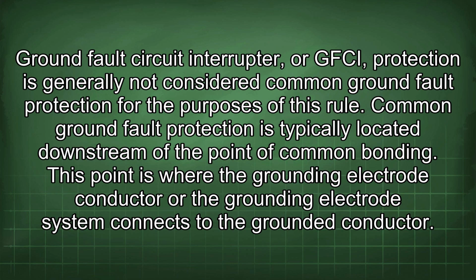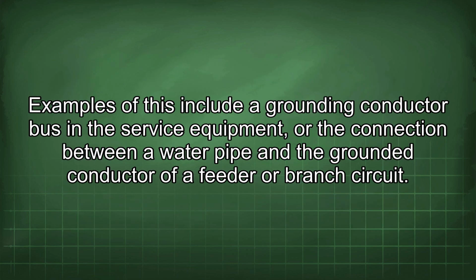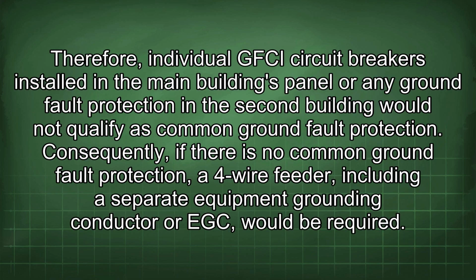Ground fault circuit interrupter, or GFCI, protection is generally not considered common ground fault protection for the purposes of this rule. Common ground fault protection is typically located downstream of the point of common bonding. This point is where the grounding electrode conductor or the grounding electrode system connects to the grounded conductor. Examples of this include a grounding conductor bus in the service equipment, or the connection between a water pipe and the grounded conductor of a feeder or branch circuit. Therefore, individual GFCI circuit breakers installed in the main building's panel or any ground fault protection in the second building would not qualify as common ground fault protection.